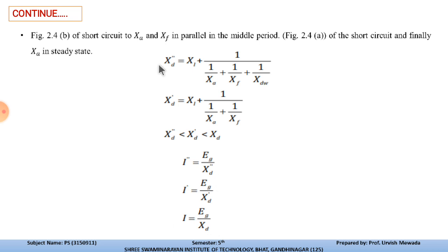Immediately after the short circuit, the symmetrical short circuit current is limited by only the leakage reactance of the machine. However, to counter the demagnetization of the armature short circuit current, current appears in the field and damper winding, which assists the rotor field winding to sustain the air gap flux.